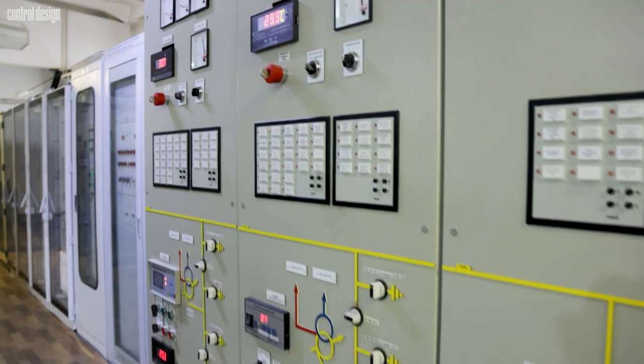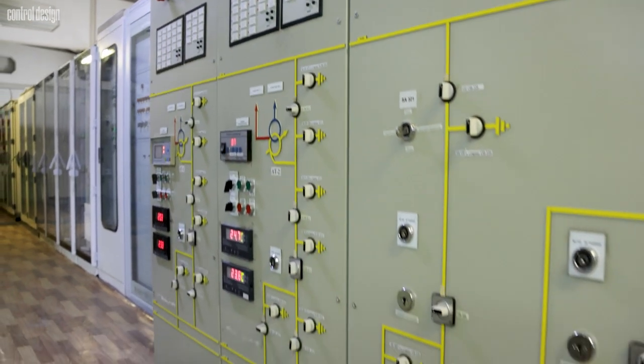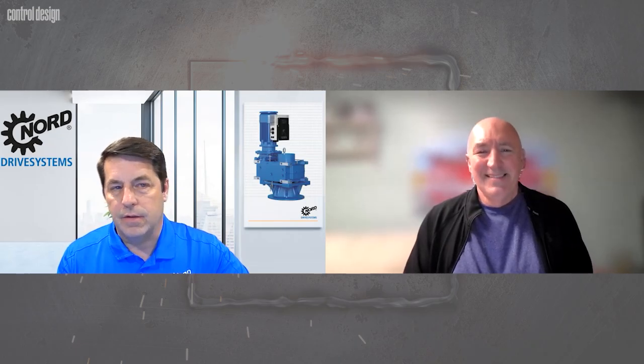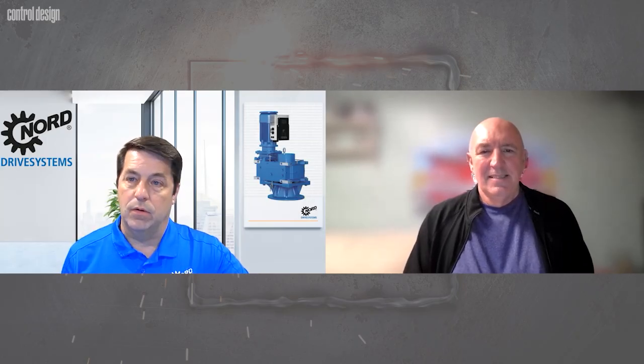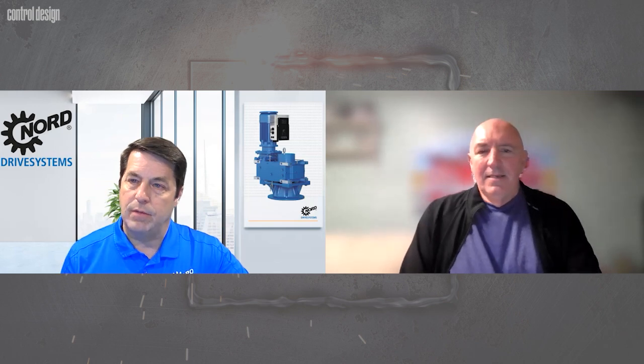That's a great question to start off with, Mike. So just to explain decentralized drives a bit, the classic drive in the control industry is in an electrical panel. It's considered an electrical device located in the electrical panel with all the other components, power supplies, PLCs, breakers, everything electrical that you would think of in that enclosure. So that's the centralized view. The decentralized drive is taking the VFD, the variable frequency drive, the motor drive, out of that electrical enclosure and moving it out onto the motor or near the motor where it's best to service that motor.